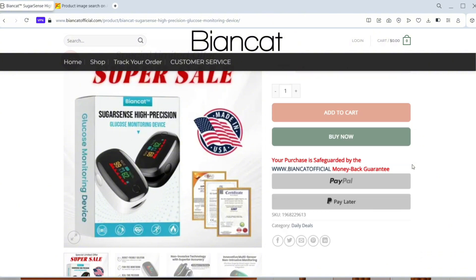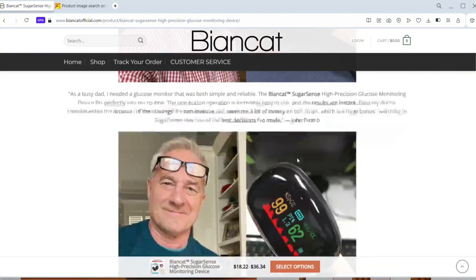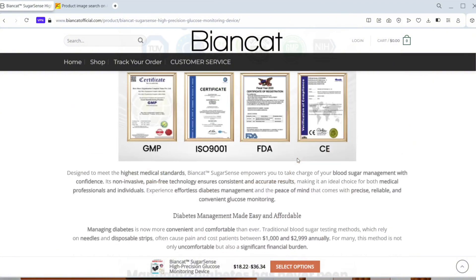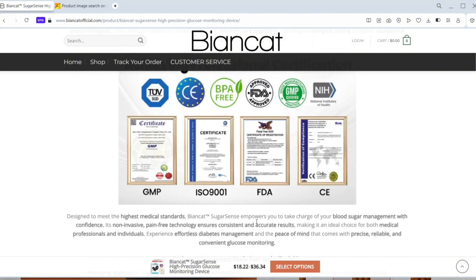They also throw around the phrase 'FDA certified.' Here's the thing: the FDA doesn't certify devices. They either approve or clear them through formal, traceable processes. Biancat hasn't shared any documentation proving either.